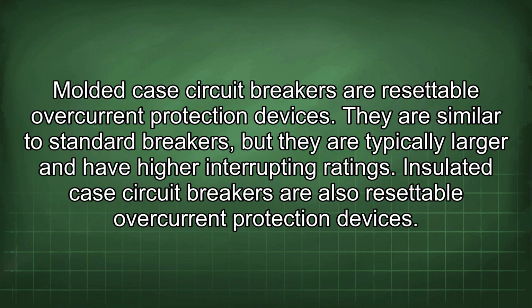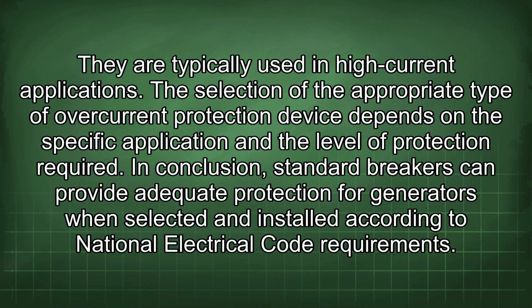Molded case circuit breakers are resettable overcurrent protection devices. They are similar to standard breakers, but they are typically larger and have higher interrupting ratings. Insulated case circuit breakers are also resettable overcurrent protection devices. They are typically used in high current applications. The selection of the appropriate type of overcurrent protection device depends on the specific application and the level of protection required.